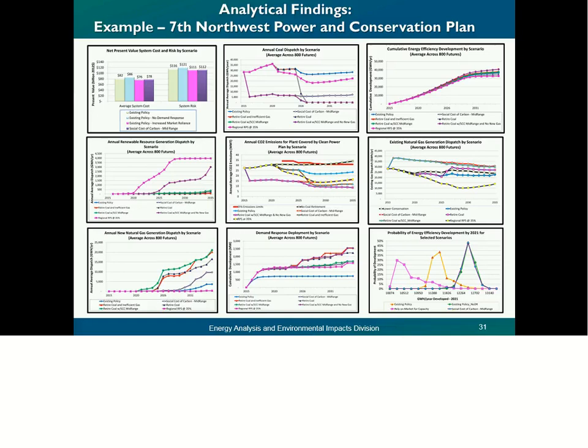But if you've got a solar farm located in far southwest Idaho, we've got to put a 230 line out there to get to it, or if we've got wind in western or eastern Montana, we've got to expand the Cross Rockies transmission, 500 kV, to get to that resource. Or we've got to close a coal plant to allow that line to take on the wind. But that's not likely to happen, so we're going to be looking at adding that transmission cost. So it's a part of getting that resource.